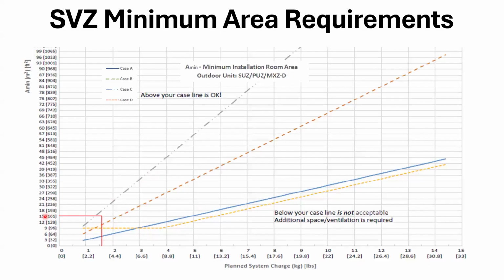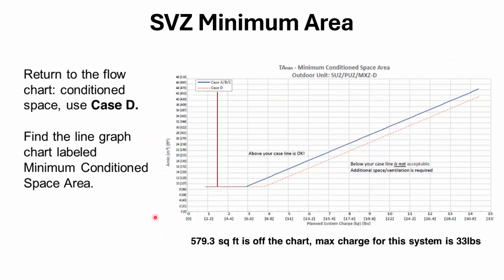So based on square footage, this is just telling you the system charge amount for that particular system. So the goal is, wherever you're putting the system in, you want to have a decent amount of square footage where that ducted unit is installed. Because it gives us the capability of having, on a smart multi, like I said, between 17 and 28 pounds of refrigerant. It's pretty common on those systems.